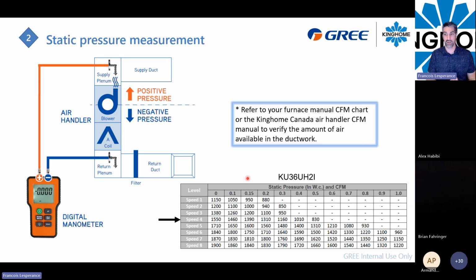I know with multiple ductwork installers, when you design your ductwork, they will design it maybe at 0.5 or 0.4 static pressure by default. So if you know exactly what your design is, if the ductwork is designed for 0.5, you will manage your fan speed regarding 0.5. But by taking the measurement, that will assure you that you don't have, for example, a clogged filter or some ductwork that is blocked in any way. So you will make sure your system is at 0.5 or 0.4.